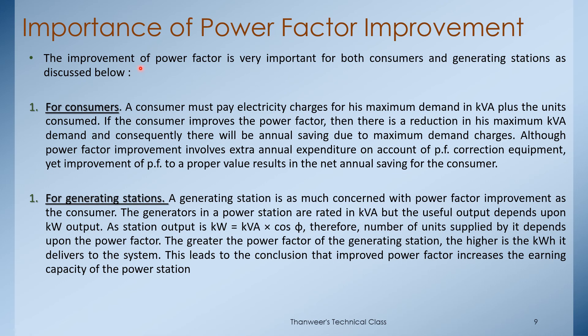The importance of power factor improvement is very significant for both consumers and generating stations. The consumer must pay electricity charges for maximum demand in kVA plus units consumed. If the consumer improves the power factor, there is a reduction in maximum kVA demand, resulting in annual savings on maximum demand charges, even though power factor improvement involves some extra annual expenditure.